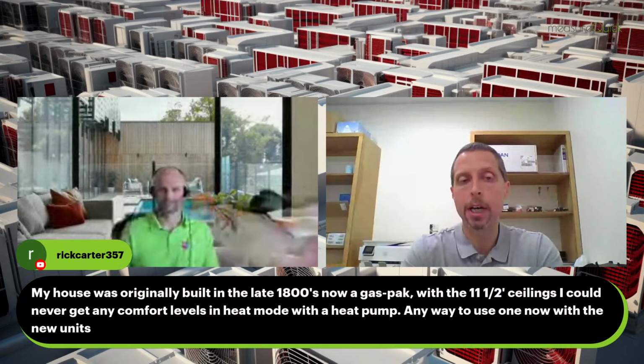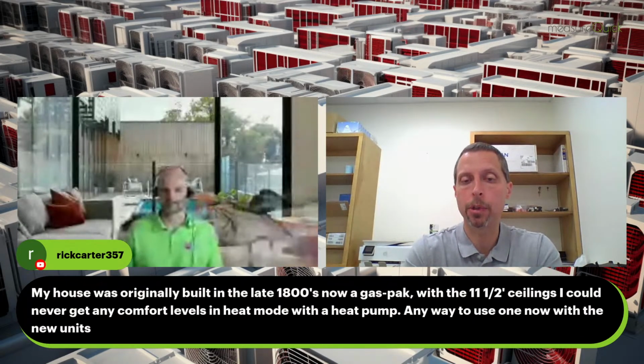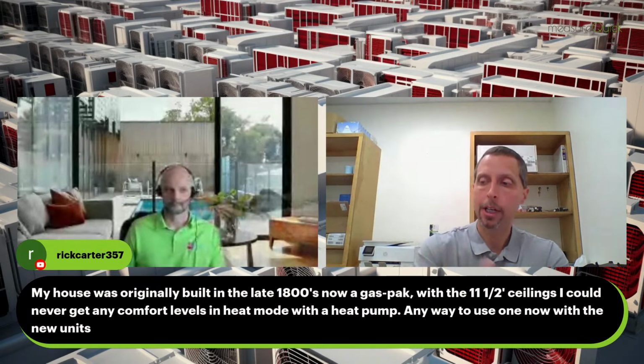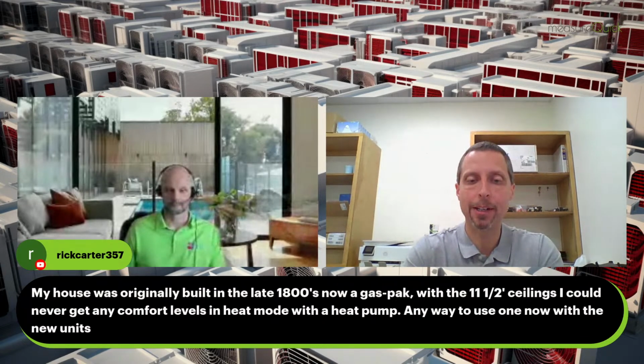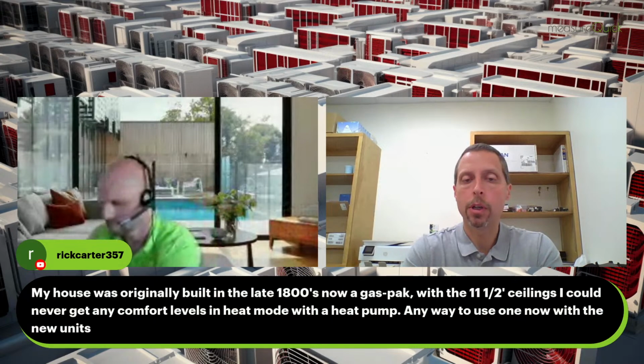On the equipment side of this, when we're looking at cold climate heat pump sizing, variable capacity heat pumps, since I got kicked off the stream here and had to log back in, we lost a few minutes. I was going to share a few slides on what we call the advanced heat pump sizing method. Unfortunately, the IT world didn't want that to happen today. But what you want to look at here is we do now have an advanced heat pump sizing method.